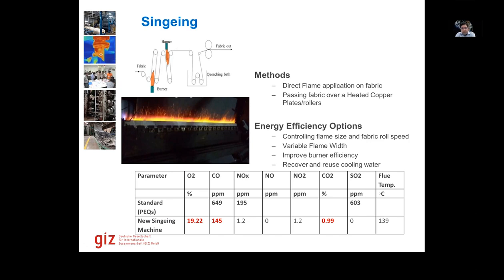Optimization will be done at the burner side, obviously - we'll have to control the air and fuel ratio. It's also important to look at the fabric quality alongside. Sometimes the burner itself is inefficient, so it's not really possible to adjust oxygen to a great extent. In that case, we have to review if the burner needs to be changed, or the blower needs to be changed, for example.